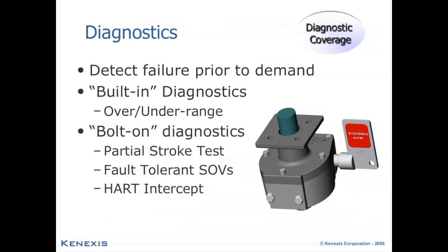Diagnostics are similar to function testing, but are different in the respect that they perform their intended action typically during process operation rather than full function testing, which is an offline test procedure.